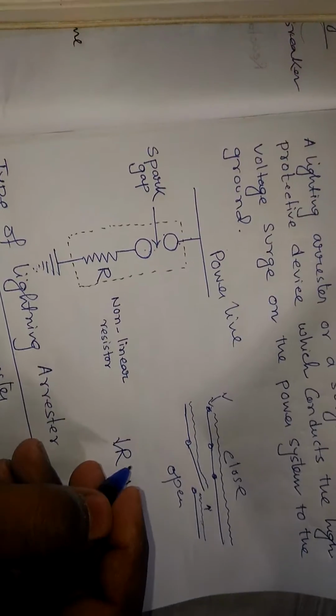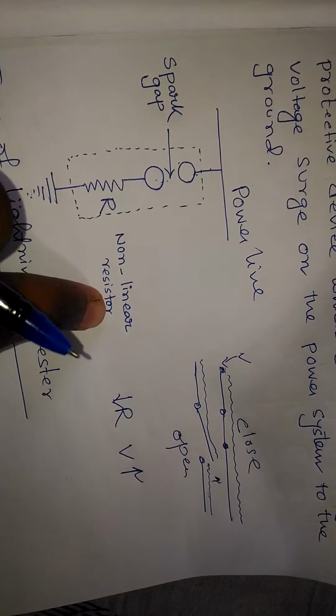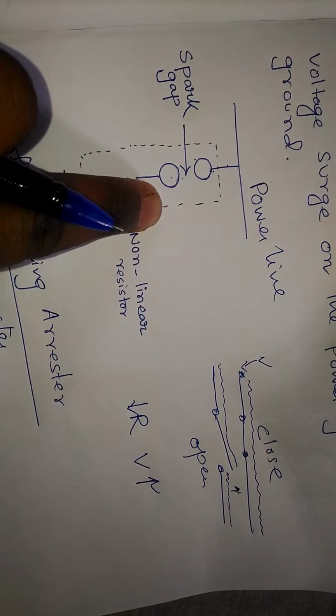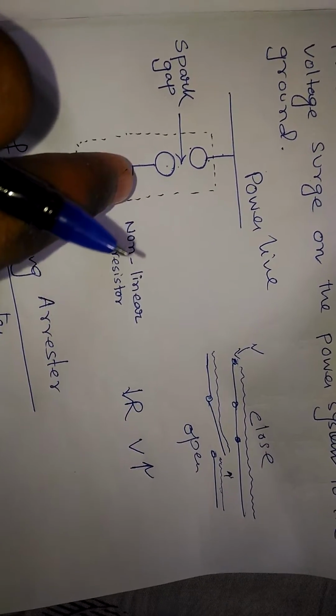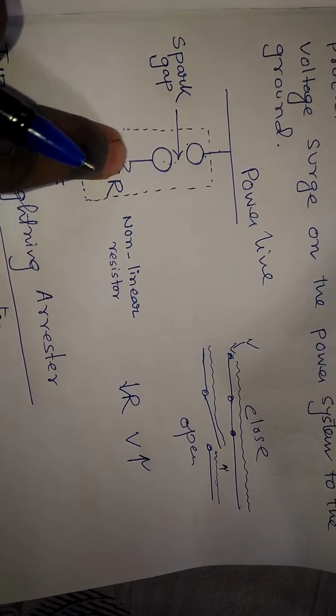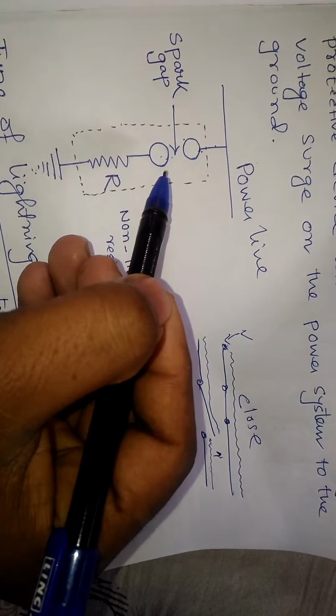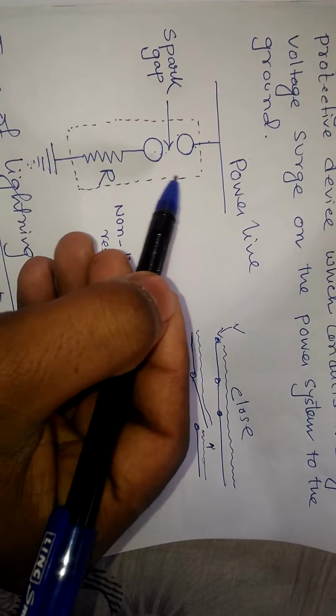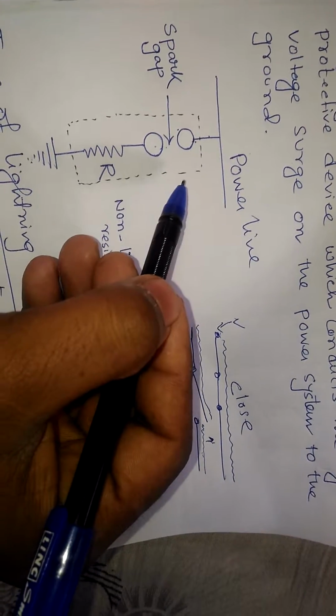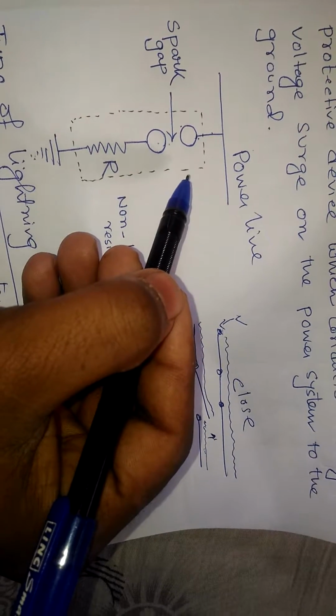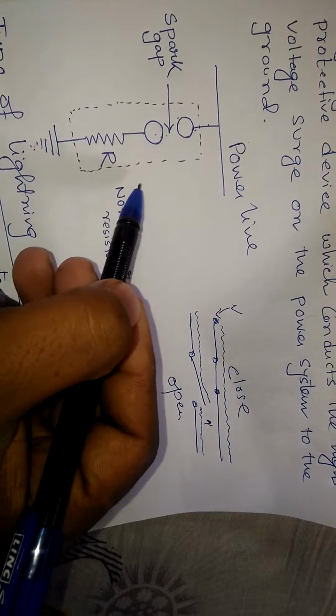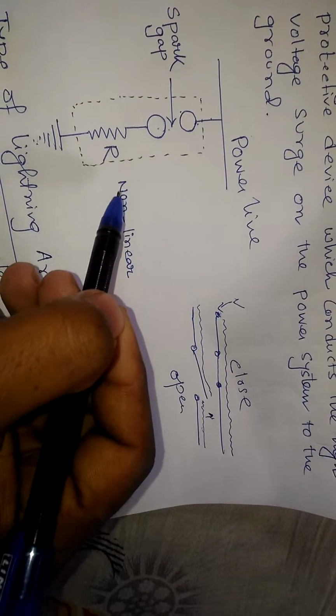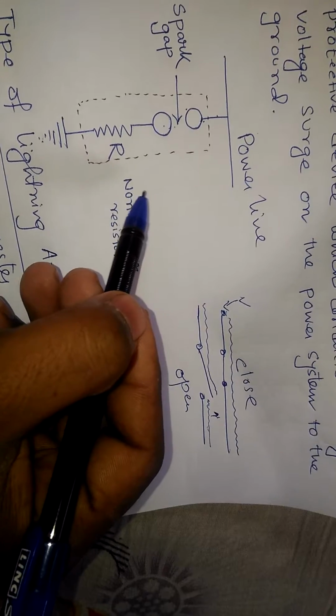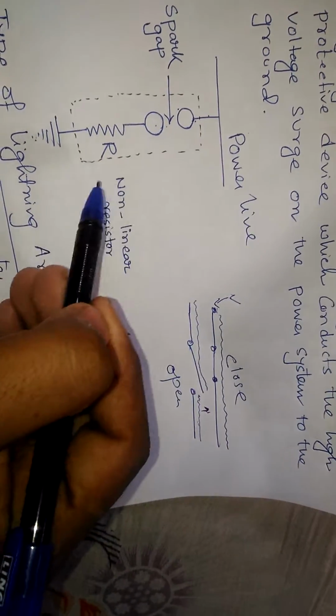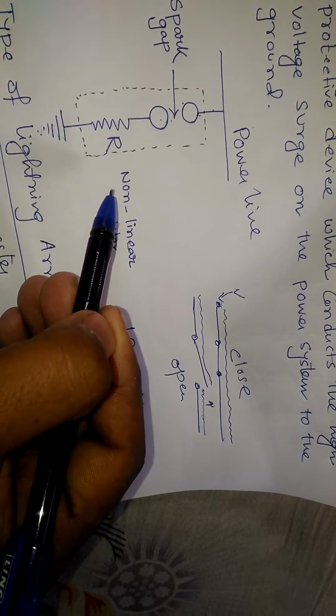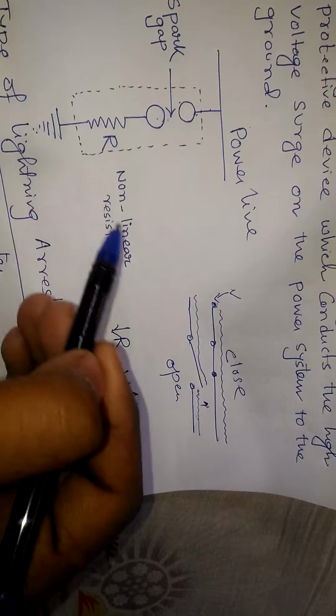So what is the action of the lightning arrestor? Under normal operation, the lightning arrestor is off in the line. It conducts no current to earth, and the gap is non-conducting. On occurrence of overvoltage, the air insulation across the gap breaks down and an arc is formed, providing a low resistance path for the surge to the ground. In this way, the excess charge on the line due to the surge is harmlessly conducted through the arrestor to the ground instead of being sent back over the line.